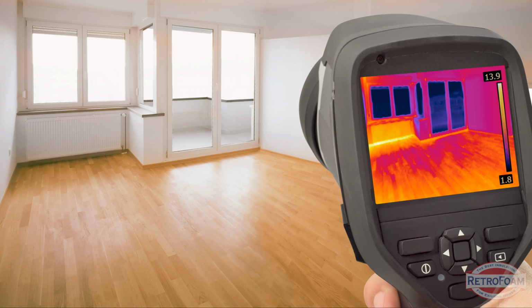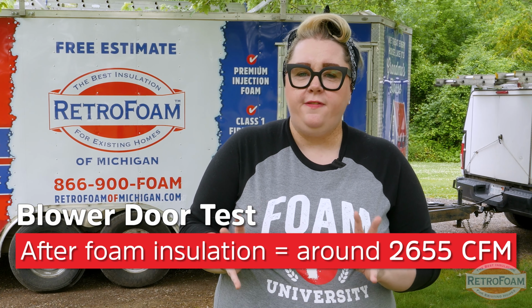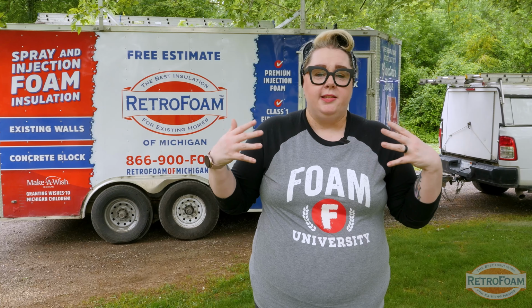The blower door test is a great tool to help us know definitively how much air is leaking out of the home. Now, I've shown you that the blower door test is the gold standard to show the energy efficiency of a home. When we started this project, the CFM was around 3,516. That second blower door test that we did shows that the CFM is now around 2655, maybe a little bit lower. So, the blower door test is hard numbers and hard proof and evidence that sealing the building envelope definitely makes a difference in the amount of air leakage in the home.